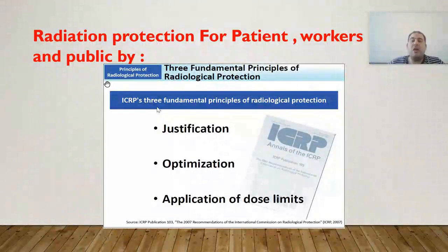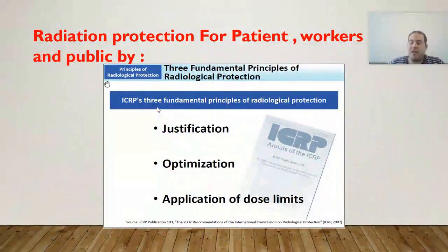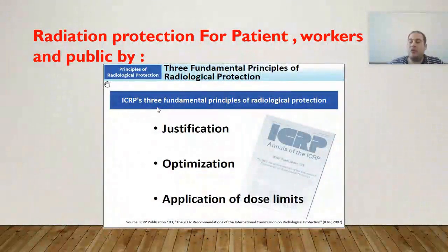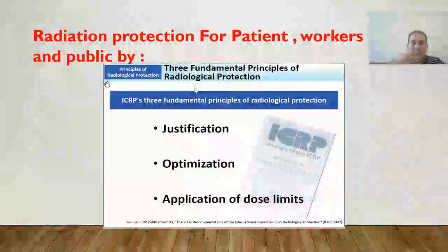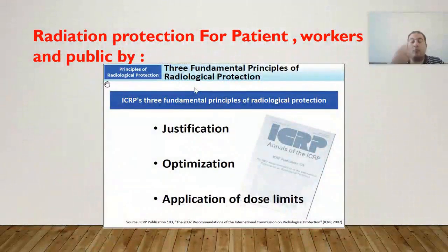The people working with you, for example, during any procedure are directly exposed in the cath lab or in interventional radiology. Whether we can perform the procedure without scattered radiation also depends on the procedure you choose during your work. The dose parameters you work with, such as kV and milliampere, need to be chosen carefully. For instance, you should consider when selecting appropriate settings for the procedure.